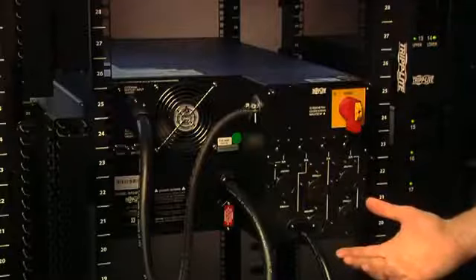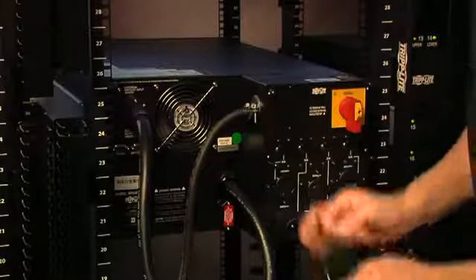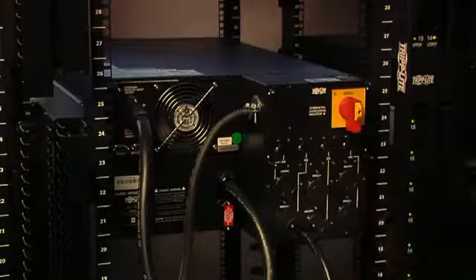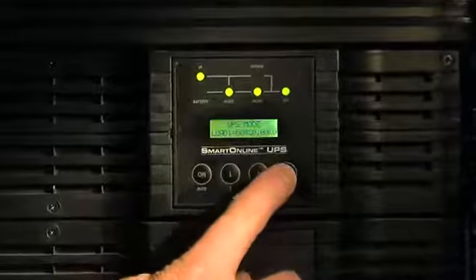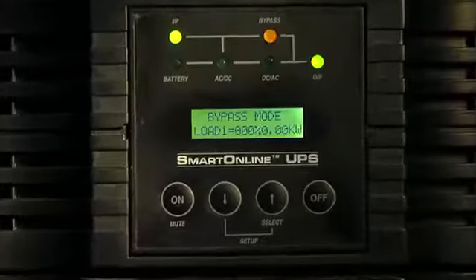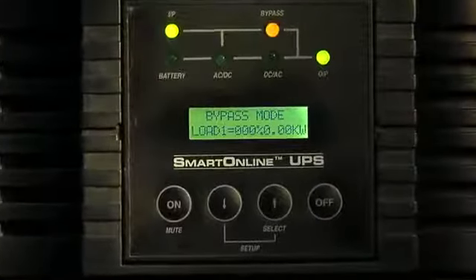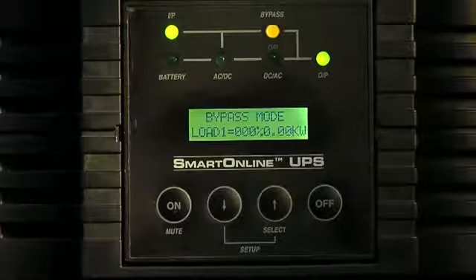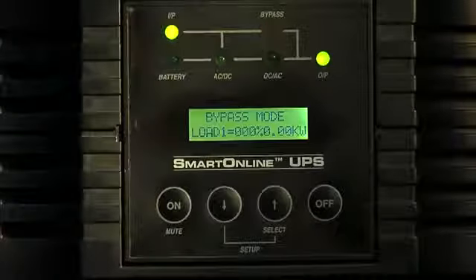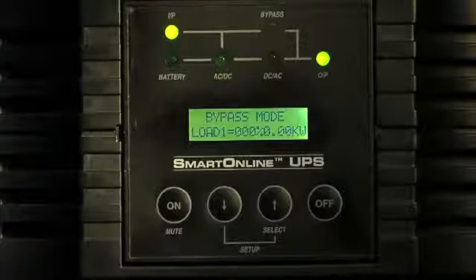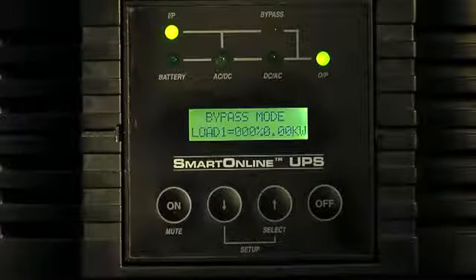So step one is to put the UPS into an electronic bypass state via the front panel. The first step in the hot swap process is to ensure that the system is in a bypass state. By pressing the off button, it shifts into a bypass state and the system is ready for the next step. Normally, if there is actually a fault, the system will automatically shift into a bypass state. Here in a simulation, we need to force it into a bypass state. We're ready for the next step.